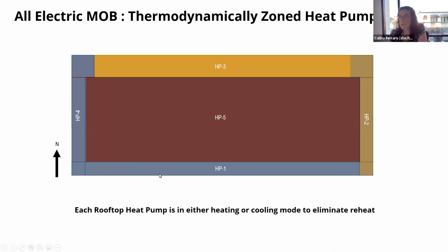On the perimeter zones, in the morning the east side warms up first, so that zone might not need heating anymore while the west side still does, and vice versa in the evening. The north is certainly cooler than the south. So we put each perimeter on its own heat pump zone, meaning each zone is only doing heating or only doing cooling, never both in the same zone.